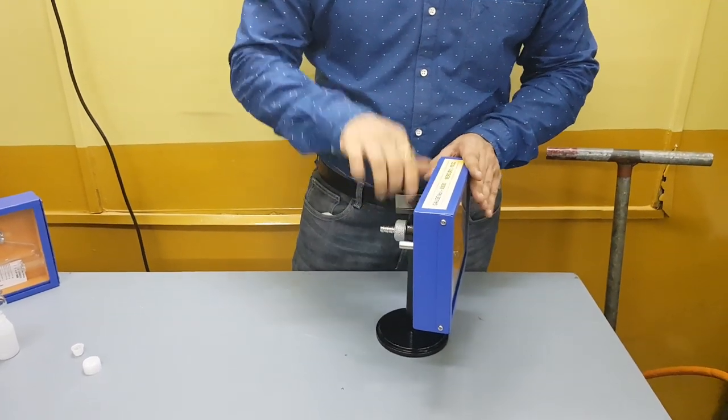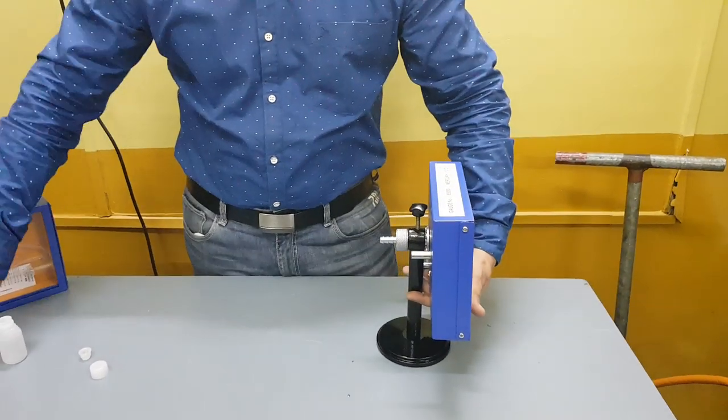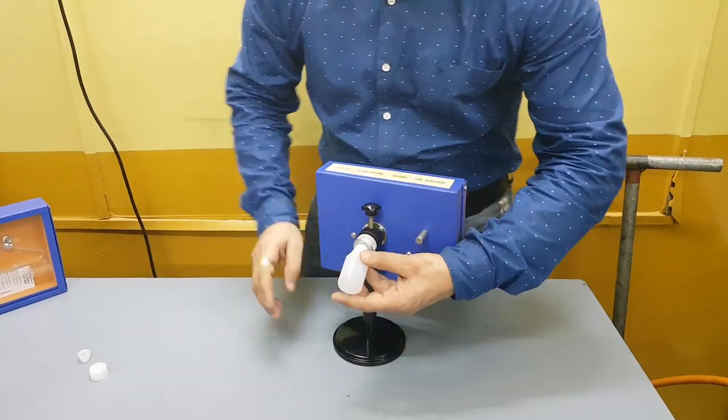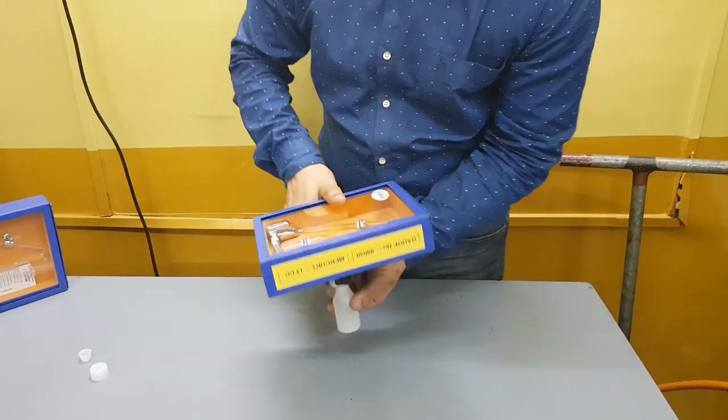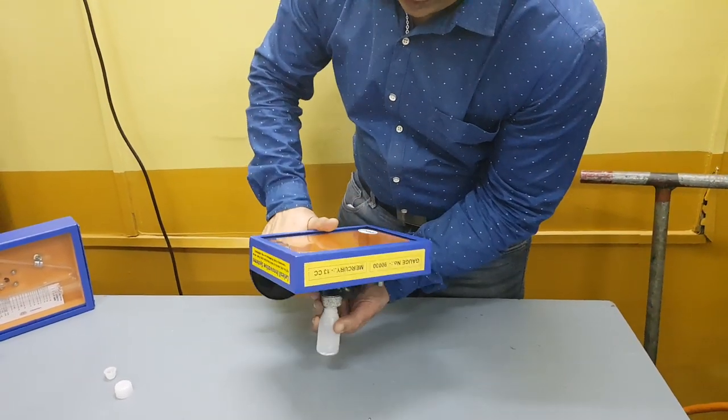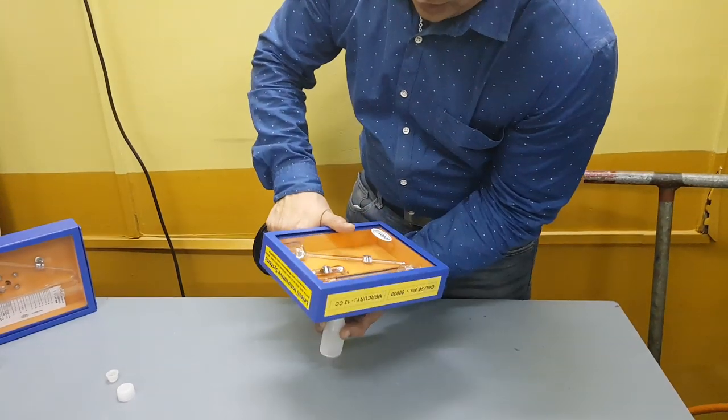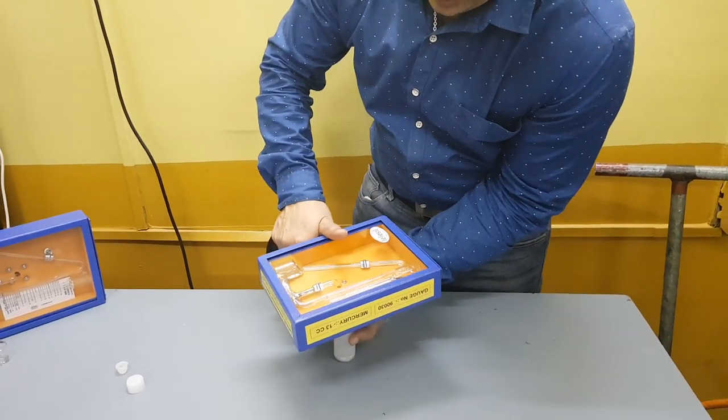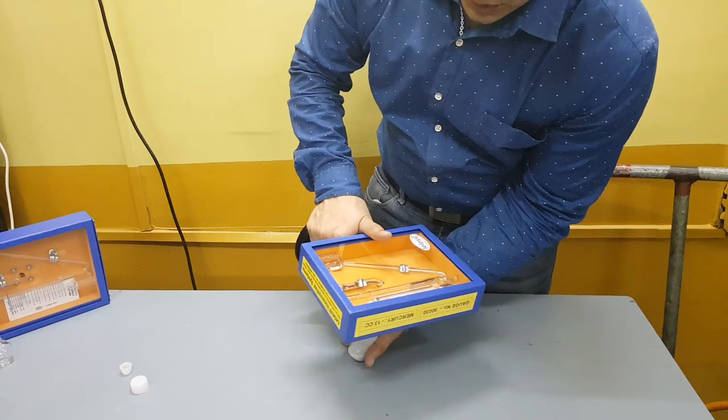When you want to remove the mercury, when you do not need to test the gauge, tilt it, connect the bottle, gradually remove the mercury back. Only do this if you have the experience to do it, otherwise there is a possibility that the quantity could spill out.